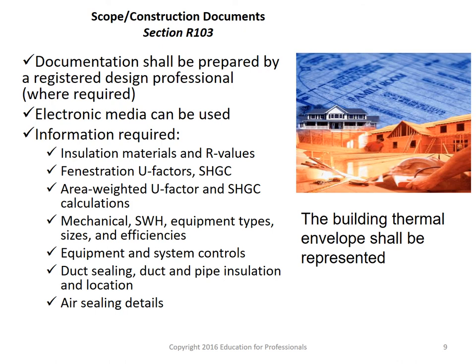Section 103 covers construction documents. Documentation shall be provided by a registered design professional where required, and electronic media can be used. At a minimum, construction documents must include insulation materials and R-values, fenestration U-factors and SHGC, area-weighted U-factor and SHGC calculations, mechanical and service hot water equipment types, sizes and efficiencies, equipment and system controls, duct sealing and pipe insulation and location, and air sealing details.